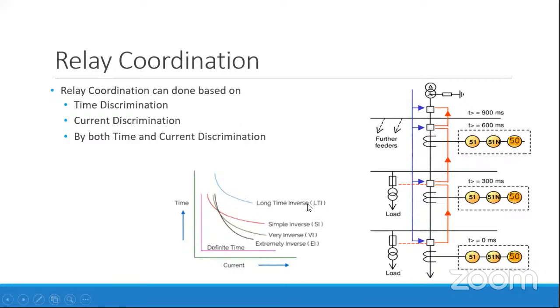To coordinate the LT network which is equipped with fuses or low voltage circuit breakers, we generally use the extremely inverse curve and the very inverse curve, as they are coordinated with the fuse or MCBs connected in the downstream network. They have such characteristics that they can match easily with the fuse and the low voltage MCBs. So we use very inverse and extremely inverse curves. And likewise for relay to relay, we use simple inverse curves and long time inverse curves to coordinate the network.